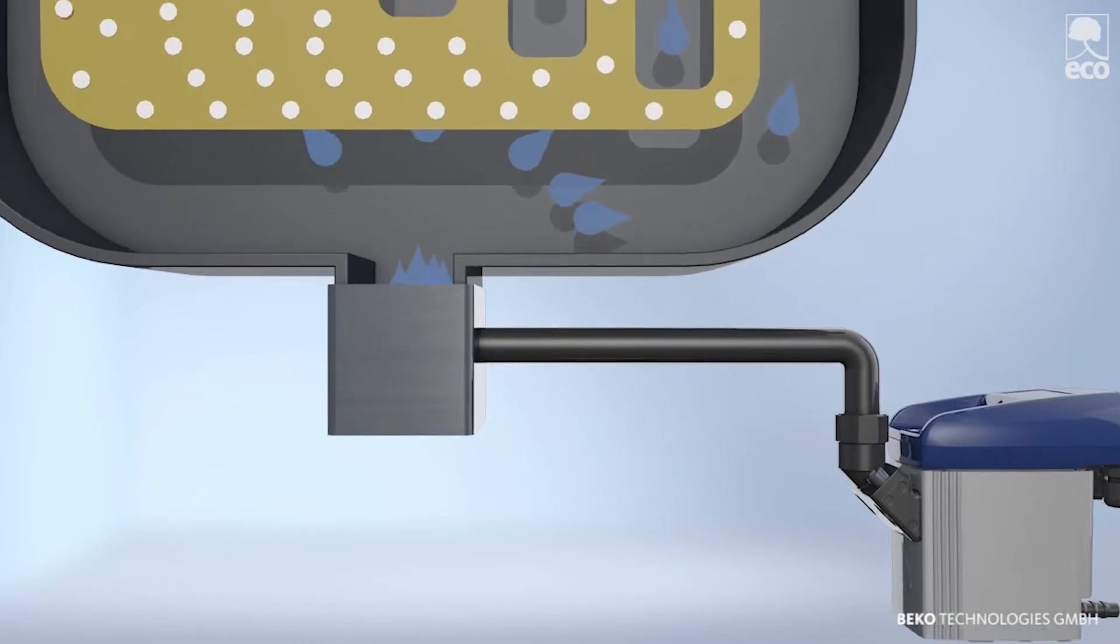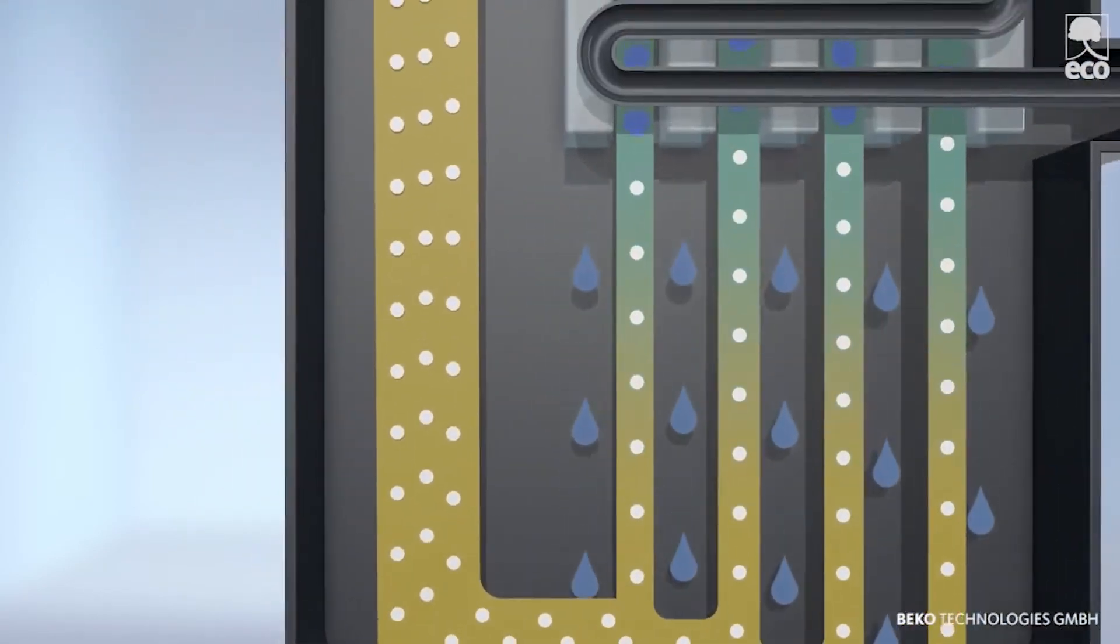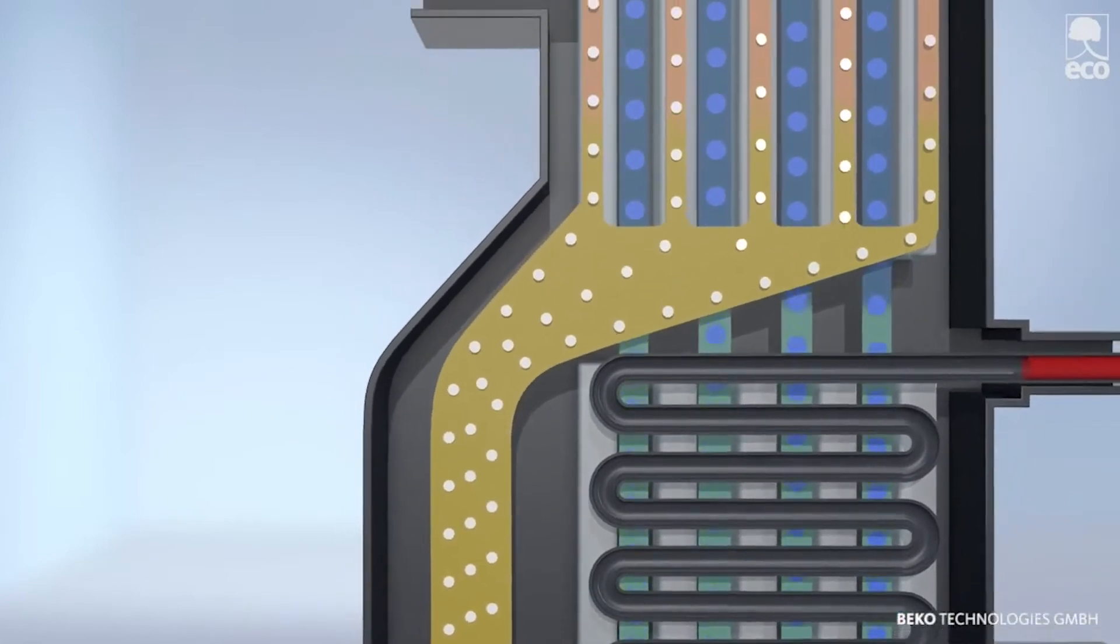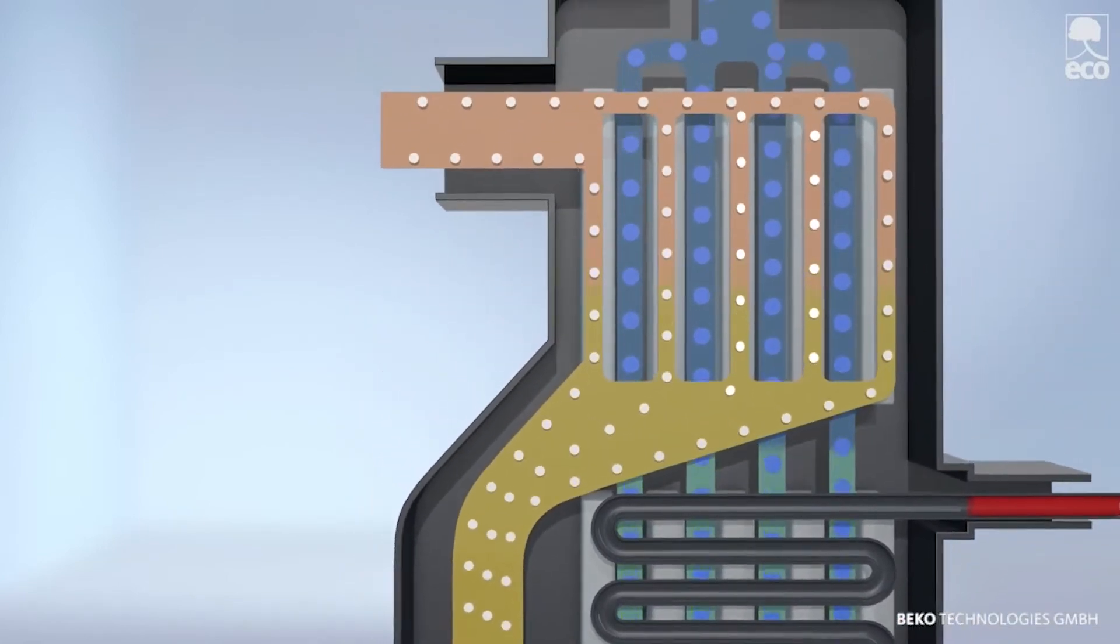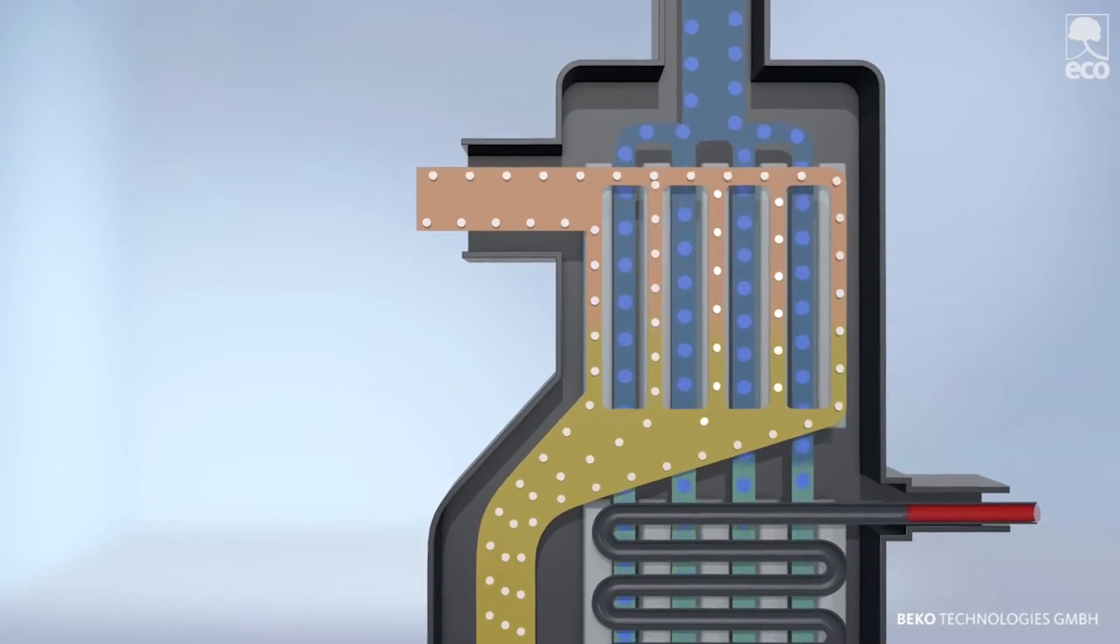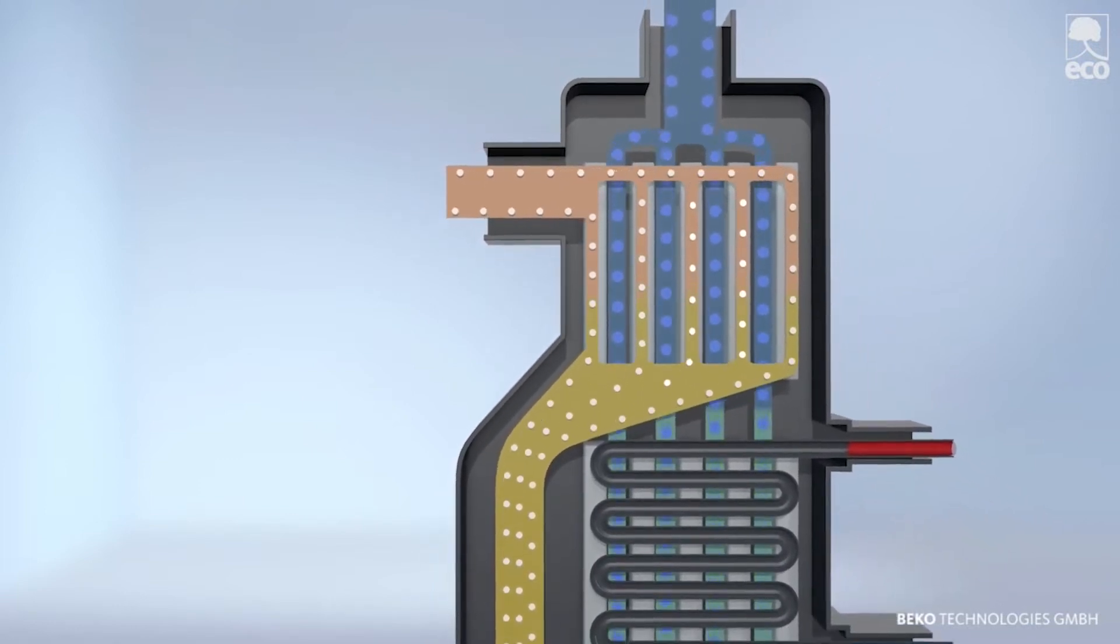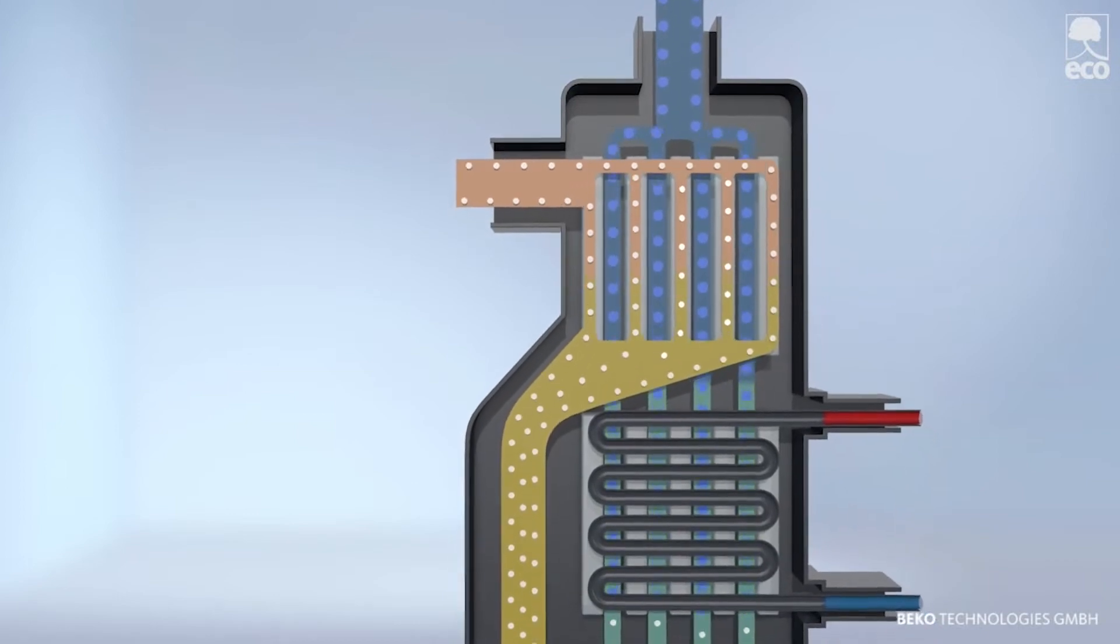The cool, dry compressed air next flows through the upper section, again past the entering air, cooling it as before in a counter-current process and is thereby reheated. This further reduces the relative humidity, making the air even drier.